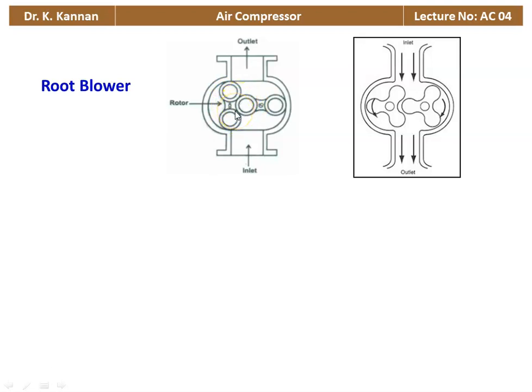The lobes and rotor are rotating, and air is entering through the inlet passage. As the air enters, it occupies the space available. As the lobe rotates, air is entrapped between the space. As the rotor rotates, the entrapped air gets compressed. When the lobe rotates by 90 degrees, the air is exposed to the outlet passage and the compressed air leaves to the discharge side. The space between the lobes and the casing is where air is entrapped, compressed, and the high pressure air is delivered through the outlet.